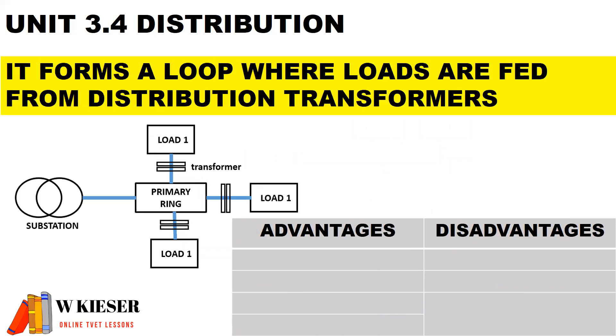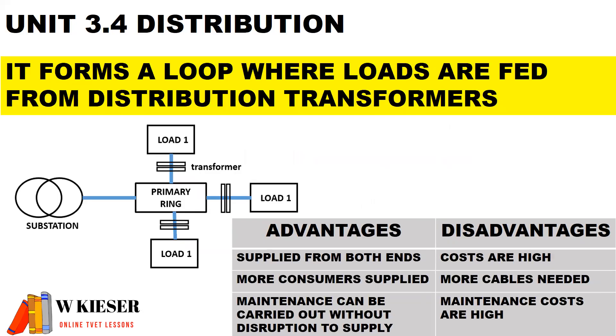For the ring feeder system, it forms a loop where loads are fed from distribution transformers. They are supplied from both ends, more consumers can be supplied, and maintenance can be carried out without disruption to the supply network. However, the disadvantages are that the costs are high, more cables are needed, and the maintenance costs are higher.